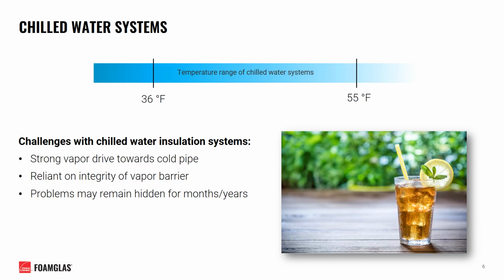Now, when we talk about chilled water systems, there's typically going to be a temperature range that we're referring to. This could be down towards 36 degrees Fahrenheit for your chilled water supply lines, all the way up to 50 or 55 degrees Fahrenheit for your chilled water return lines.